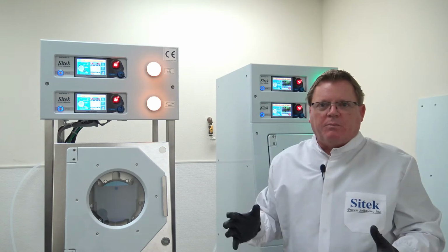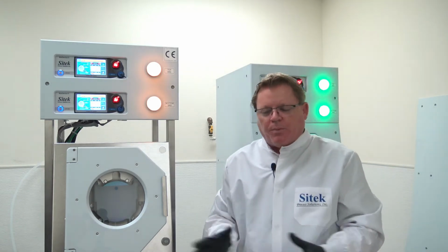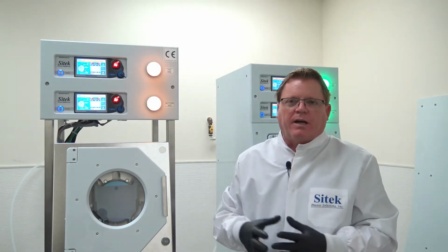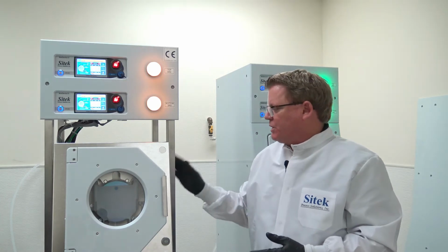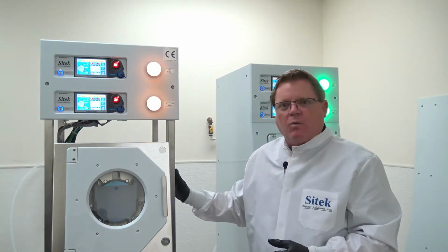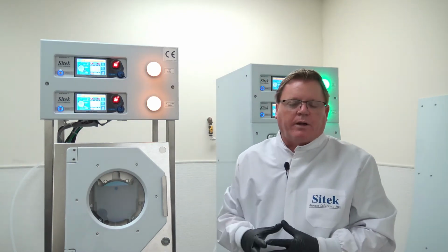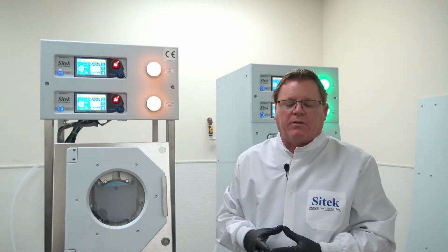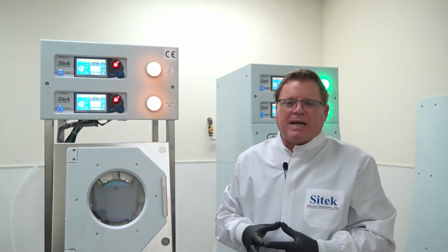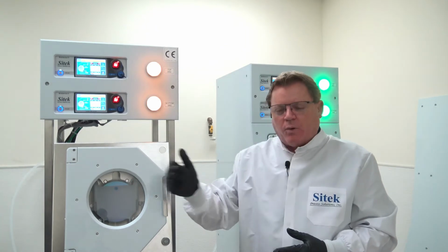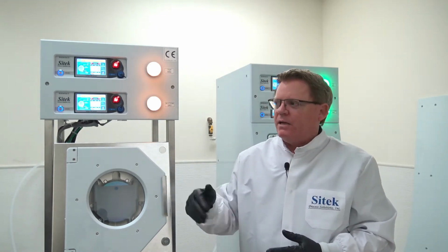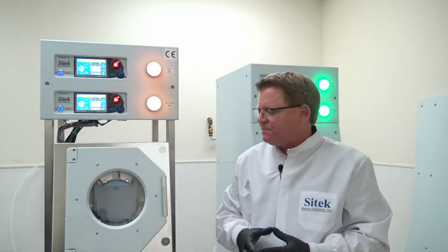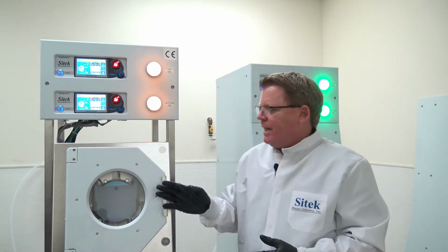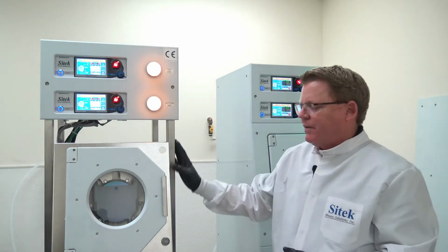So basically we build a tool up from scratch. We pre-prep all the parts, then we start building it up. We build it up on our stainless steel tables in our manufacturing area. Once a tool is built up, we have a quality control checklist that is then confirmed by another technician. If the head passes quality control, it then moves into wet test. If it doesn't, for any reason, it is reworked and then tested again. When it comes into wet test, it comes in just on a stainless steel table, not like this.